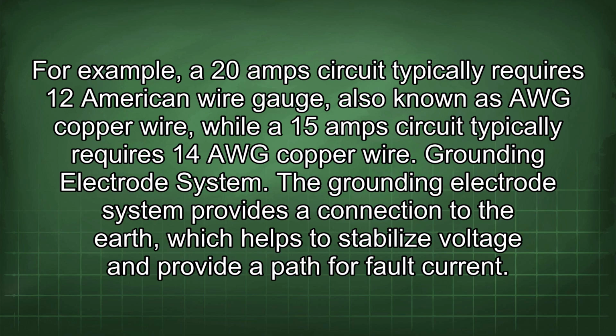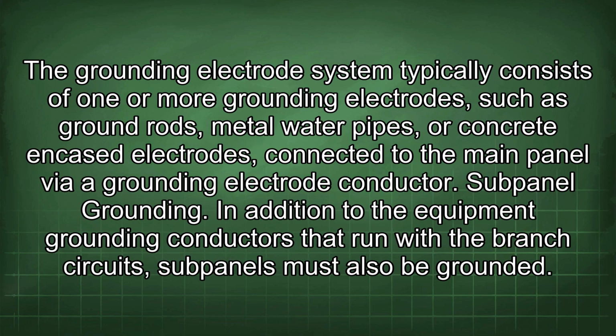Grounding electrode system. The grounding electrode system provides a connection to the earth, which helps to stabilize voltage and provide a path for fault current. The grounding electrode system typically consists of one or more grounding electrodes, such as ground rods, metal water pipes, or concrete encased electrodes connected to the main panel via a grounding electrode conductor.